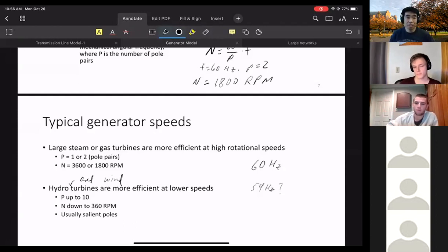Because the generator is controlled by a feedback loop on how fast you turn the shaft, right? So there's a prime mover, and you have to turn that. That really fights against something that's not designed at its natural frequency. So it's very hard to change that frequency by even 1 hertz. What a generator does is go a little bit slower, a little bit faster. But for a large frequency change, what happens? You have this torsion in the prime mover that's just twisted like this, because the grid is trying to slow down and your mechanical feedback loop hasn't caught up yet. You have something twisting at 60, this twisting at 50, so you have this kind of rotation.